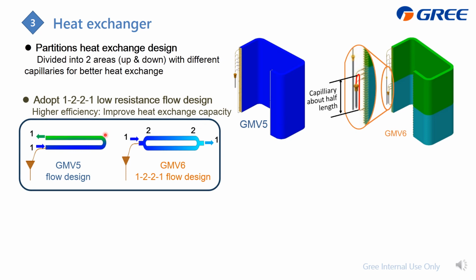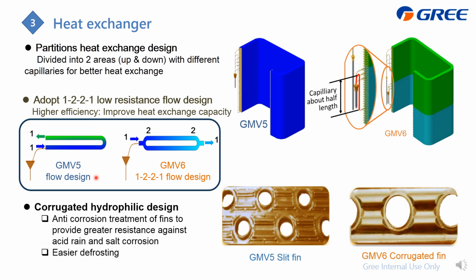And the next is from the distributor to the outdoor heat exchanger. For GMV5, the flow is only one, and it become only one. And for GMV6, we adopt this from here, it is one, and then divide into two, and then here we combine these two together and make it to be one. So from this design, we can higher the heat transfer efficiency and also amount, either from the simulation or from the test results.